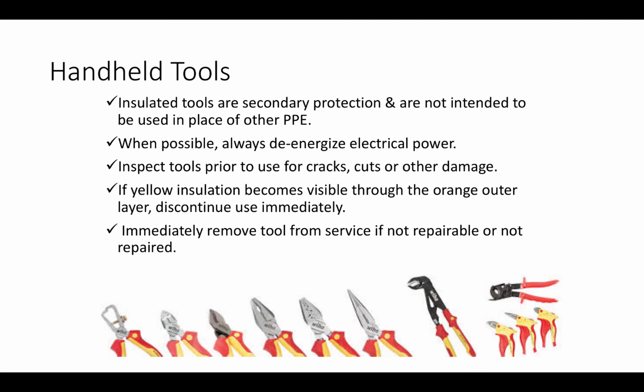With handheld tools, insulated tools are the secondary protection and are not intended to be used in place of other PPE, which is personal protective equipment. When possible, always de-energize electrical power. Inspect tools prior to use for cracks, cuts, and other damages. If yellow insulation becomes visible through the outer orange layer, discontinue use immediately.